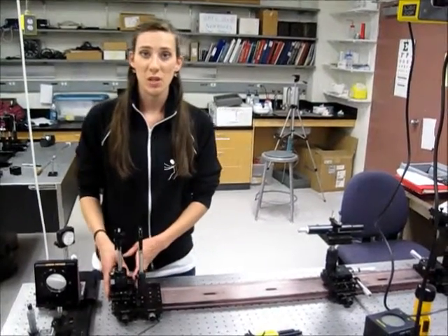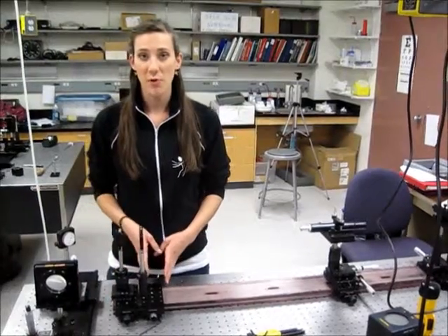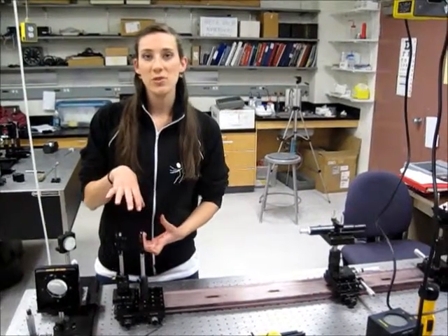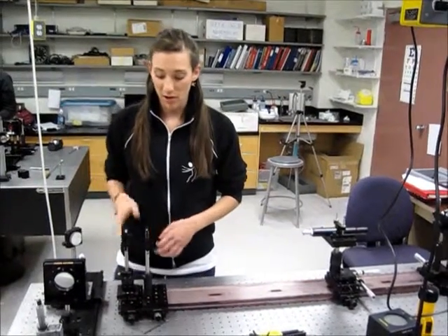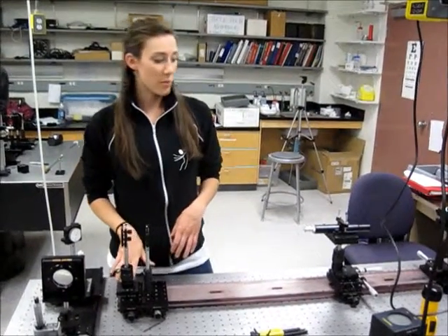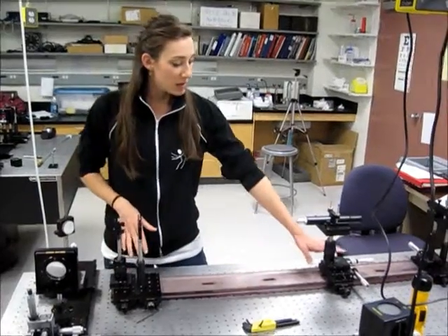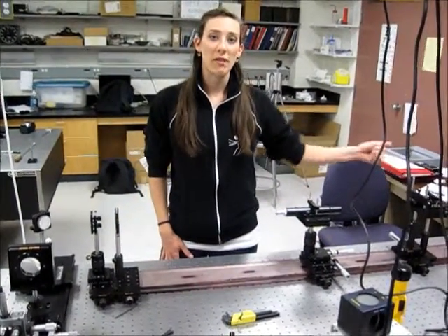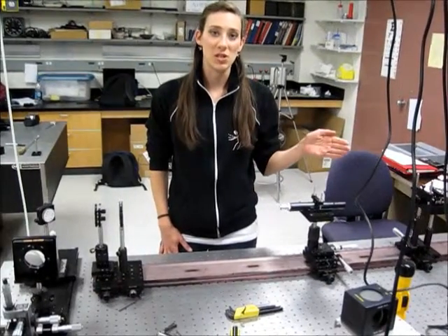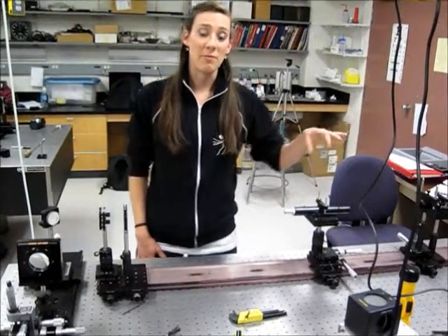In the next section, we put a test lens in just before the aperture. What we used the aperture for was to stop down the lens even more and change the F number. This lens had a focal length of about 1 meter. We then took the objective and put it at the focal point and found a few defocus positions in order to get the proper MTF.